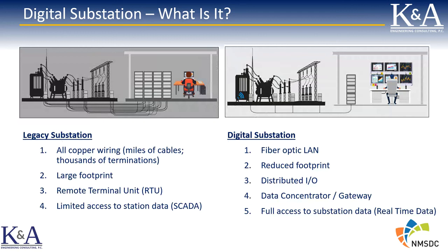So to start out with, we'll just do a quick comparison between a legacy substation and a digital substation. If you were to visit both of these types of substations, you'd find some immediate obvious differences. In the legacy substation, all the signals and measurements and alarms and so on, everything runs on copper wiring. There are miles and miles of copper wiring.